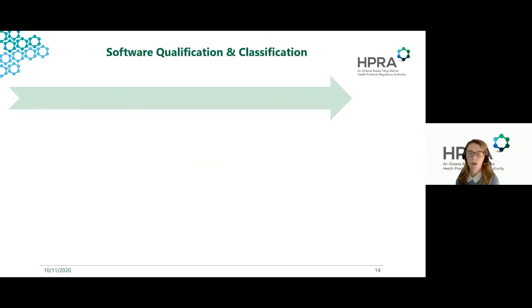So now we're going to look a bit at software. In terms of software, we need to think about qualification as well as classification. Qualification as IVD software must be established prior to application of the classification rules. You need to start again with defining the intended purpose as before. A detailed intended purpose ensures a correct qualification, and the outcome of the qualification will lead then to the classification.